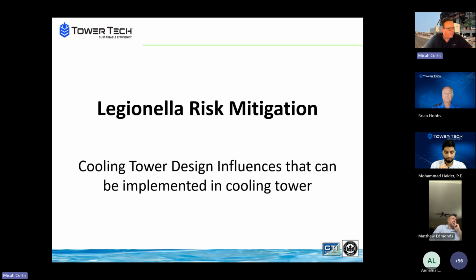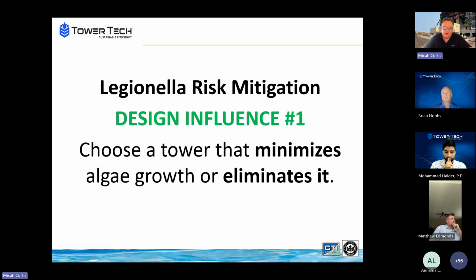So let's get into the meat of what we want to talk about, and it's minimizing the risk with all this background information about Legionella and Legionella in cooling towers. Let's talk about some design influences that can be implemented in cooling towers across, I'm not going to say all, but most manufacturers. And let's get into the nitty gritty here of what we want to talk about. So, number one is talking about the influence of choosing a cooling tower that minimizes algal growth or eliminates it.